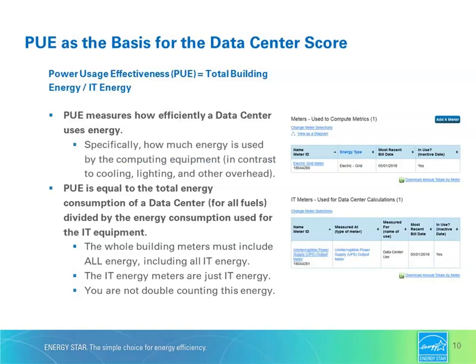So the obvious corollary to that is that the minimum theoretical value for PUE is 1.0. That's what would happen if 100% of the building energy went to IT energy. The data center in that case would obviously be dark, and it would need to have really good passive cooling in place to hit that minimum, since that means no energy is going towards anything else like lights or HVAC. That's why it's a theoretical minimum. No data center actually gets to 1.0. Some get pretty close, though.